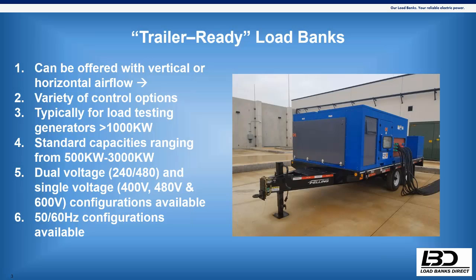These units are offered in dual voltage, so 240, 480, 208 configurations. The larger gear, 2.5 meg to 3 meg, we only offer in 400, 480, and 600 volt configurations, just based on the available space we have to work in. Dual voltage isn't offered at those larger capacities, and you typically don't see 240 or 208 volt generators bigger than around a megawatt or so, just generally speaking. So that's kind of a driving factor there as well. But we do offer the dual voltage, so you can go out and use it on pretty much any generator, as long as it's a 208 or 480 volt generator, which gives you a wide range of applications, compared to a single voltage load bank where you're stuck only being able to test either a 480 volt or 600 volt generator.